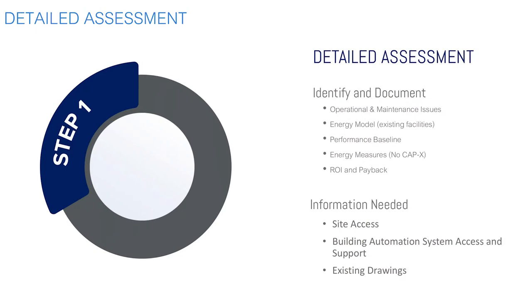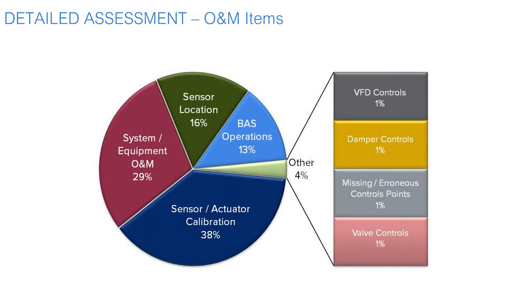As part of the assessment, we test every single system, point to point. We command every valve, every damper, we put our eyes on it. We command it 0%, 25%, 50%, 75%, 100%. We want to make sure that whatever the control system thinks it's doing, it's actually doing in the field, and we record that. For this specific hospital, about 38% had sensor calibration issues. If you're a control person, you know junk in, junk out. If the system is giving me wrong information, no matter how good the programming is, the control is going to be inaccurate, least to say. Same thing, we had some deferred maintenance, about 29% of items. And then you have sensor location, where the control vendor had actually installed sensors in the wrong location, and nobody was the wiser, so to speak.